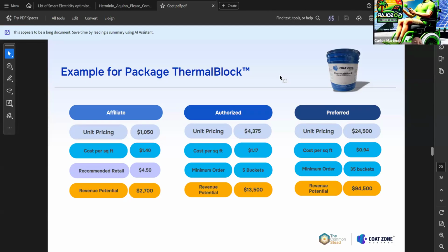I'm interested in seeing what that combination's offset is going to be. Realistically, with the optimizer, you're normally looking at around 20% on commercial, roughly. And with this, we've done it so many times, like the one I showed you with Johnson Controls in Saudi Arabia, that was 12.7% according to their testing on the energy consumption of that actual HVAC. If you say roughly 15%, and 60% of your energy in that building is HVAC, you're looking at roughly another 9-10% on top of your 20% with the optimizer. So you can definitely hit that 30% mark.